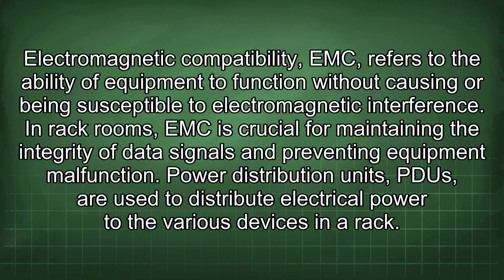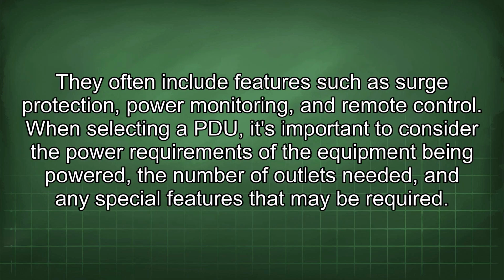Power distribution units, PDUs, are used to distribute electrical power to the various devices in a rack. They often include features such as surge protection, power monitoring, and remote control. When selecting a PDU, it's important to consider the power requirements of the equipment being powered, the number of outlets needed, and any special features that may be required.